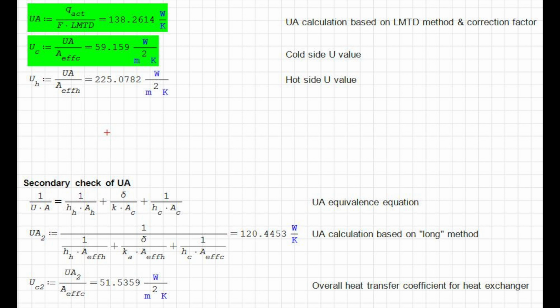For grins, if you divide the UA by the effective hot fluid surface area, then you end up with 225. So the secondary check of UA is through the long method, which is the sum of all fluids together. So you have 1 over the convective heat transfer coefficient times the surface area, plus the thickness of material over the cross-sectional area of the material times the K value of the material—this would be the aluminum plate.